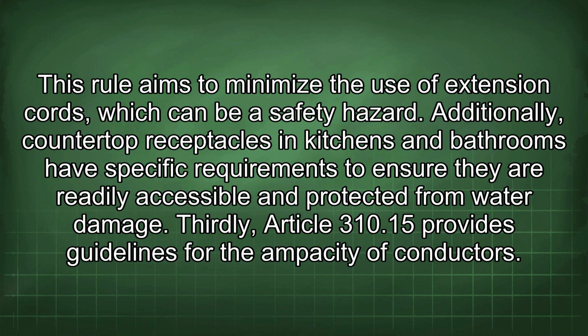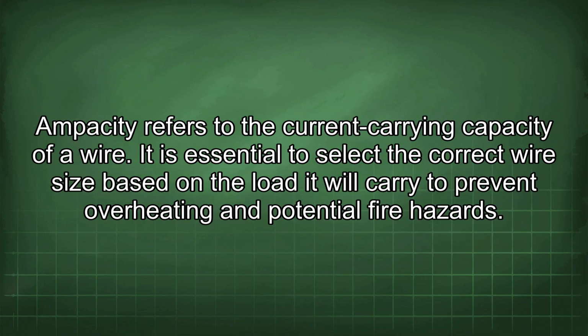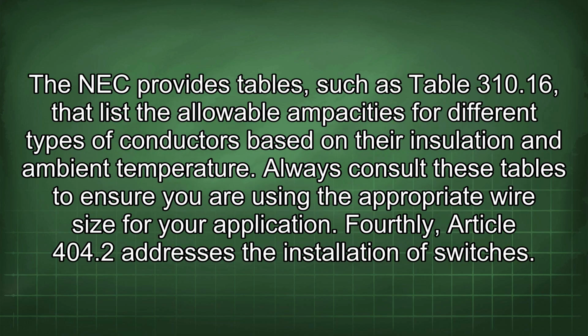Thirdly, Article 310.15 provides guidelines for the ampacity of conductors. Ampacity refers to the current carrying capacity of a wire. It is essential to select the correct wire size based on the load it will carry to prevent overheating and potential fire hazards. The NEC provides tables, such as Table 310.16, that list the allowable ampacities for different types of conductors based on their insulation and ambient temperature. Always consult these tables to ensure you are using the appropriate wire size for your application.